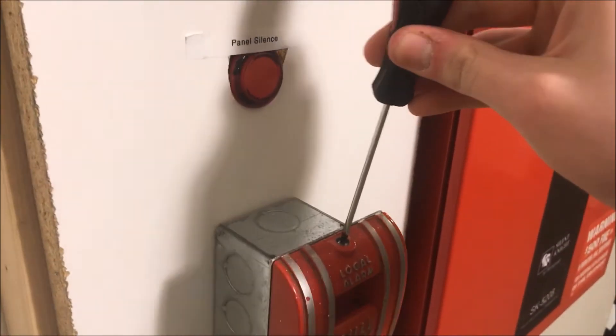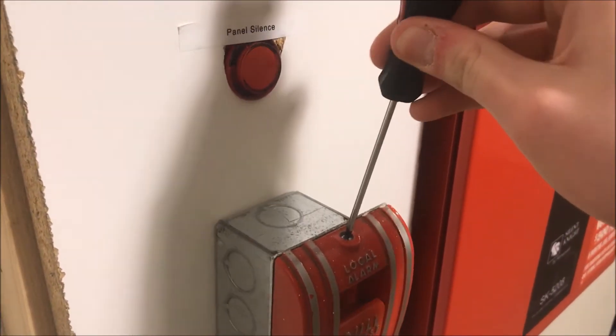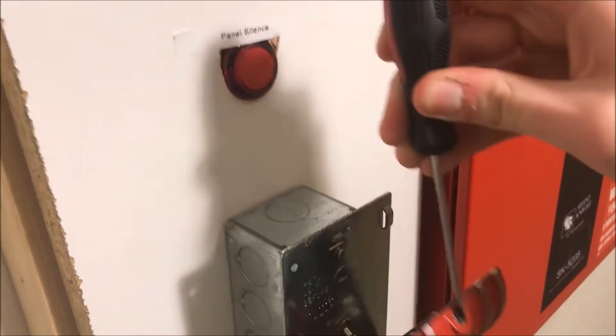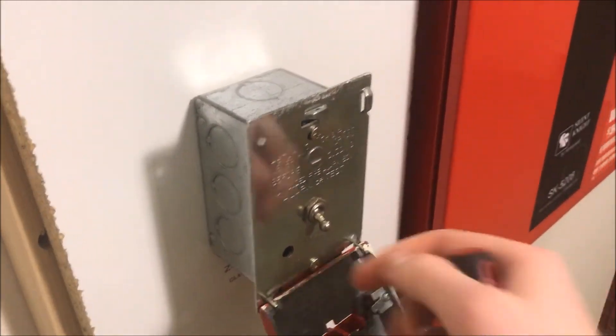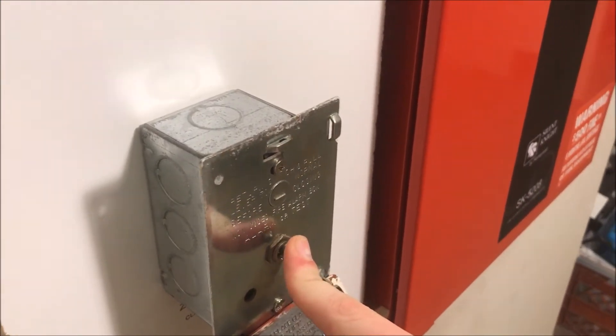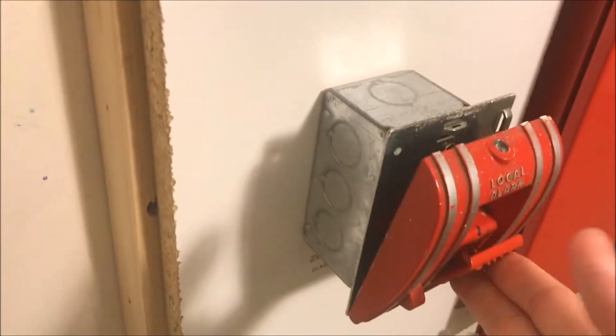All right, let's tool-test the Edwards here. So this would be like if you have a break rod in it — open it up, falls to the ground, you turn on the switch. See, it didn't do it, but if I push in... It's just got a bad switch in it, that's all.